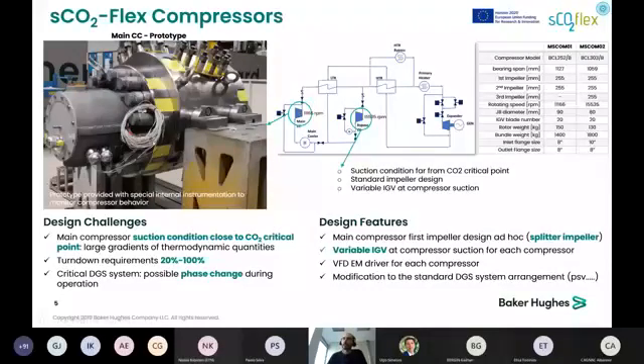Here we can see the prototype we have designed and machined in our facilities, equipped with special instrumentation inside to monitor compressor behavior during test. It is a barrel-type compressor with 2 stages, bearing span just above 1 meter, running at a rotating speed around 11,000 rpm for a pressure ratio of 3. So it is a high power density machine. Power density is the power to inertia ratio, and this is a benefit coming from using supercritical CO2 as working fluid, a clear advantage in terms of plant footprint, cost, and overall cycle efficiency.